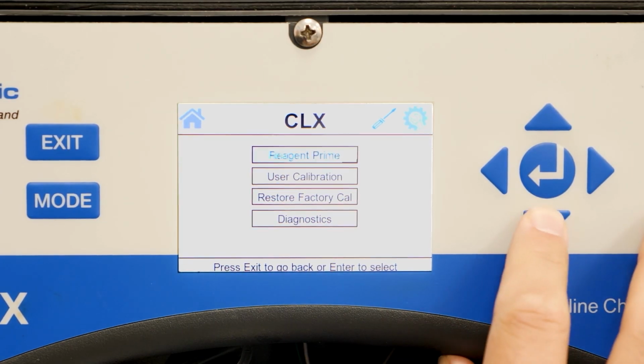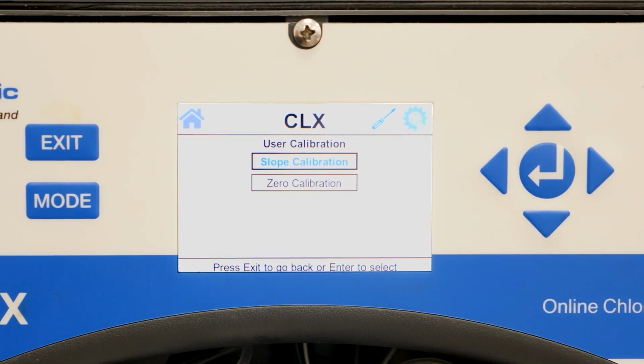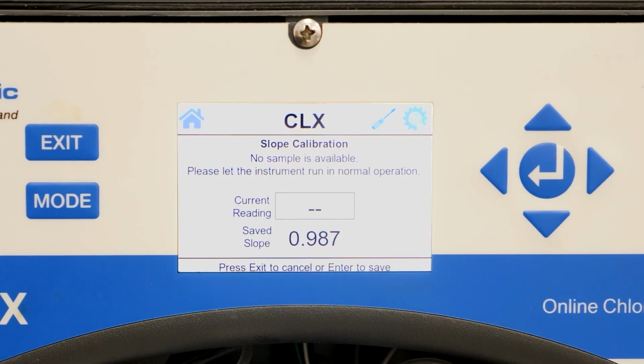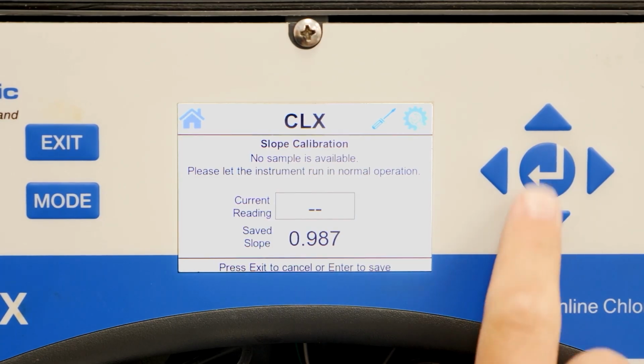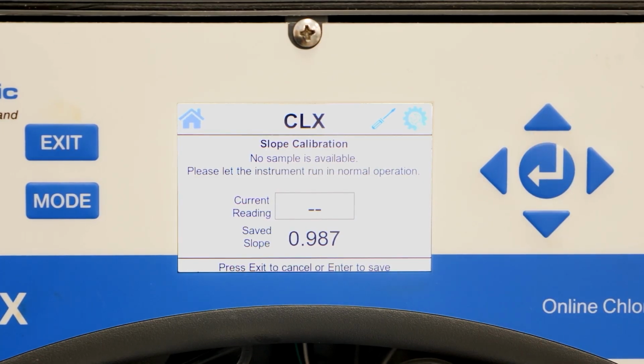The next is user calibration. The analyzer is factory calibrated. However, if you want to match it up to your handheld, the analyzer allows you to make changes. To do so, select user calibration, then select slope calibration. Adjust the number on the screen using the up and down arrow keys to match your handheld, then hit enter to save. If you are going to perform a user calibration, take the handheld sample at the analyzer to ensure that you have an accurate sample.